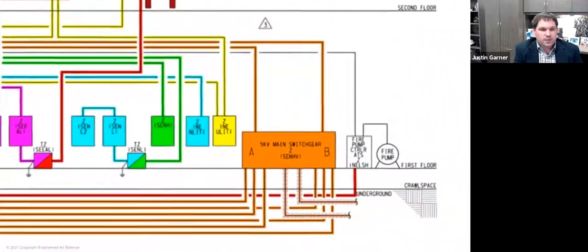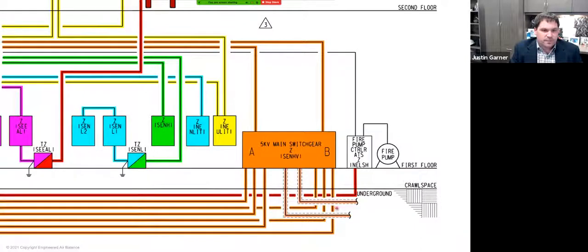So we're going to start here with the point of utility connection. If you notice here, we have some underground feeders in this particular facility that were being brought in from a utility vault directly from the utility. This happens to be medium voltage switchgear. It was 4160 volts, or 5 kV is kind of what they're normally referred to. But it could be any range of medium voltage.